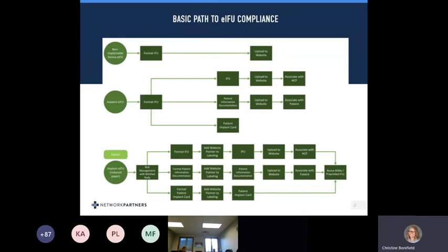The EU MDR is very clear. EU MDR Annex 1, Chapter 3, Section 23.1: Instructions for use shall, if the manufacturer has a website, be made available and kept up to date on the website. The extent and the details of this requirement have some nuances.